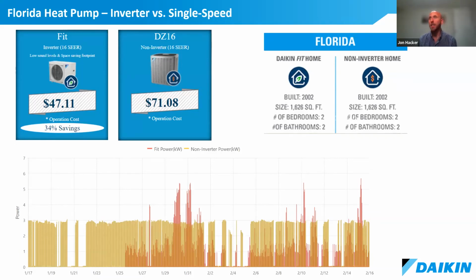So we've got modulation, we've got the ability to vary the capacity of the heat pump, but really what I think is important to call out, for the most part, looking at this data, we can see that for most of these bars, the power consumption of the inverter product, which supposedly has the same efficiency, is significantly lower. So it's operating at a much better efficiency level.